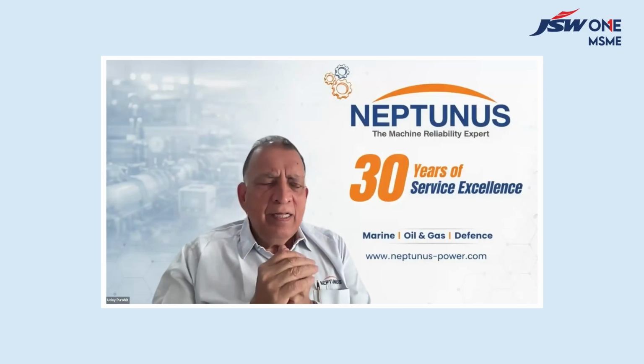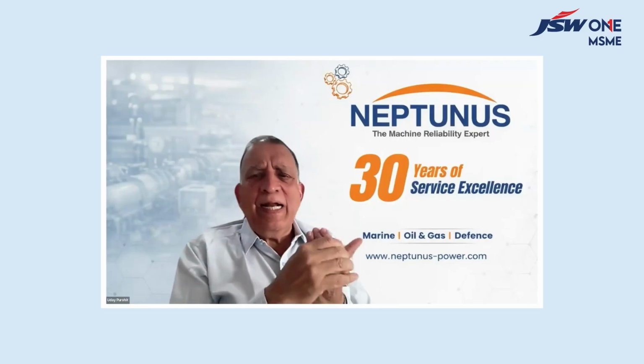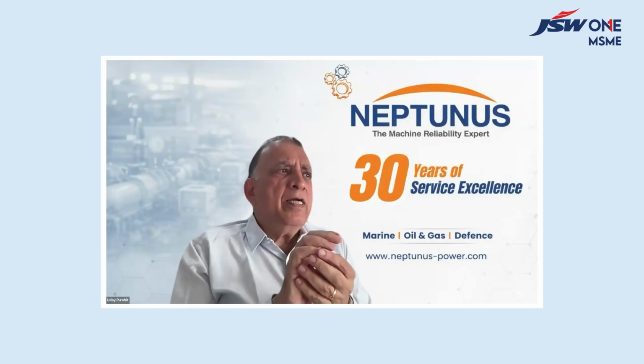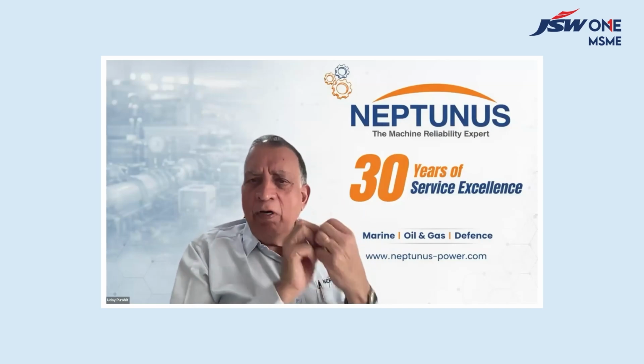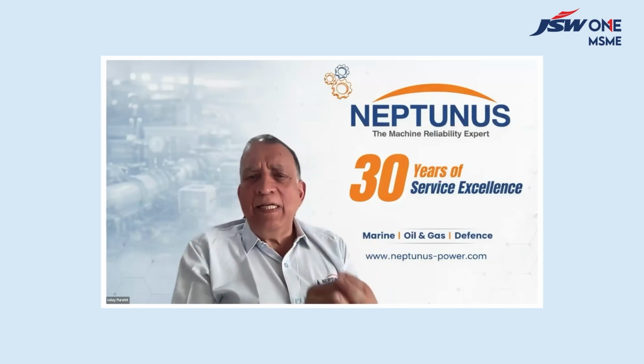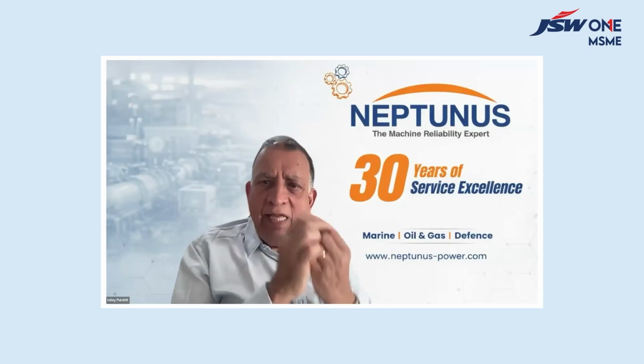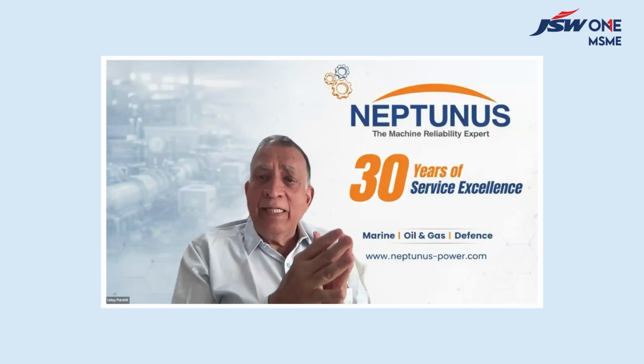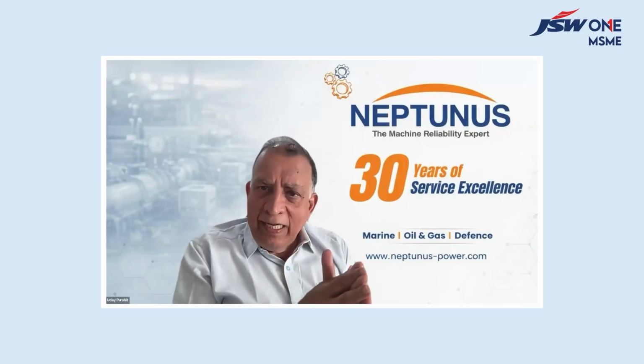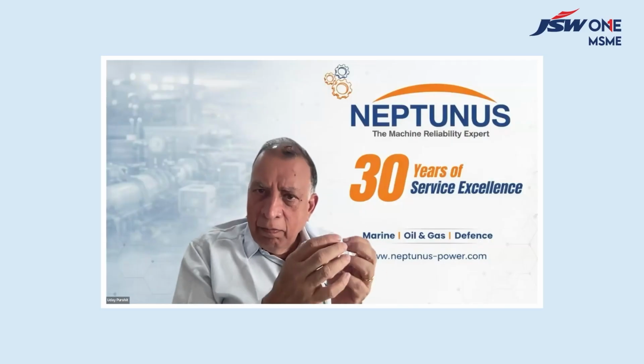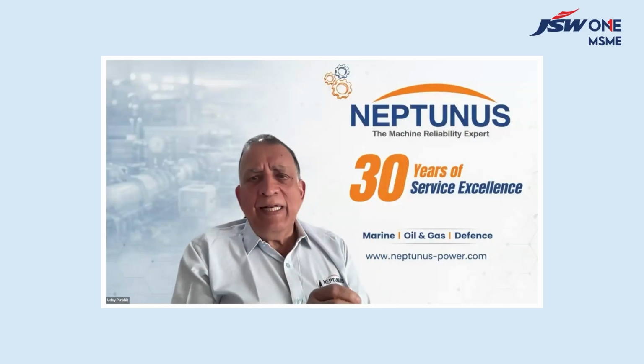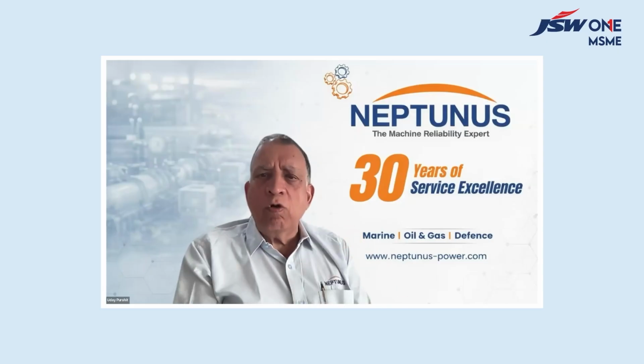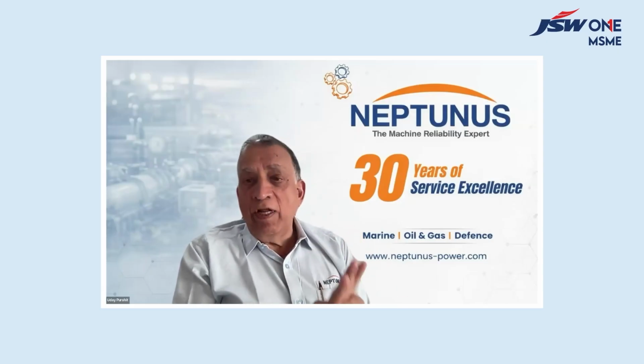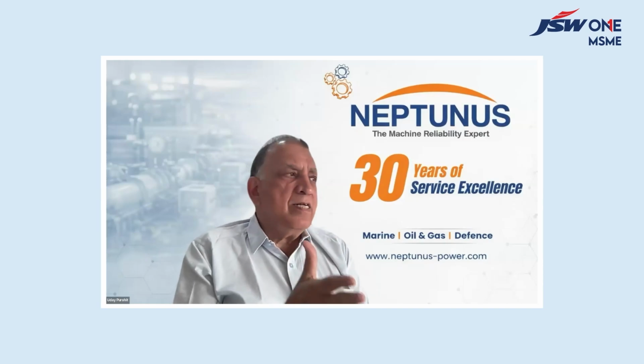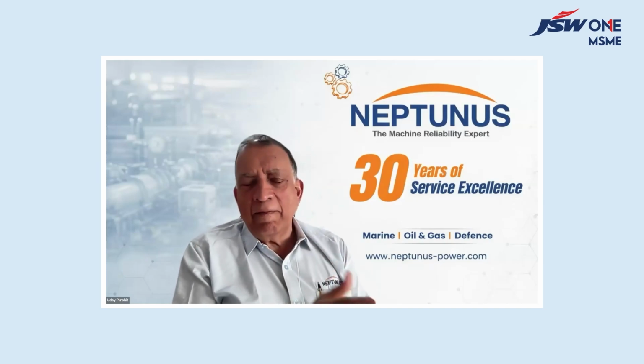So, very quick idea there: you can have leak detectors, ultrasonic machines. Importantly, if you've got machines that have oil in them, please send samples regularly for testing to an outside lab. This will give you results that tell you whether there's extreme wear and tear, whether your oil is degraded, or whether it's in good working condition. Oil analysis and oil testing are simple, low-cost methods. Once again, sorry if I keep stressing it, it's a question of habit, culture, and hygiene.